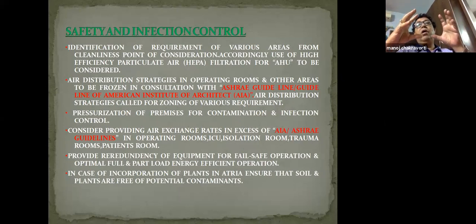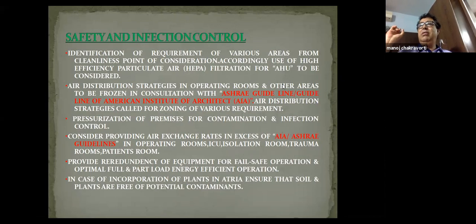If the requirement of the AHU comes down, automatically my chilled water requirement comes down, so across the coil, the in and out delta T will be coming out less, and that signal will be going to my chiller, and the chiller will start bypassing. After the secondary pump, it will start bypassing chilled water, and more bypass chilled water and return chilled water will mix.